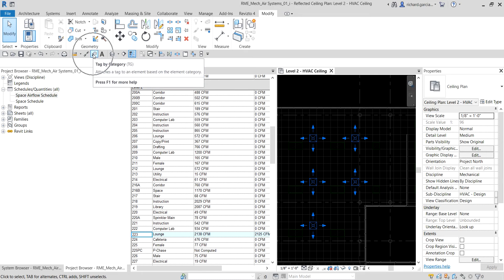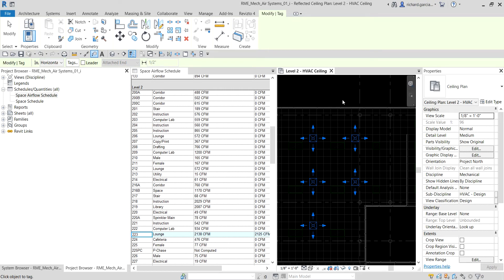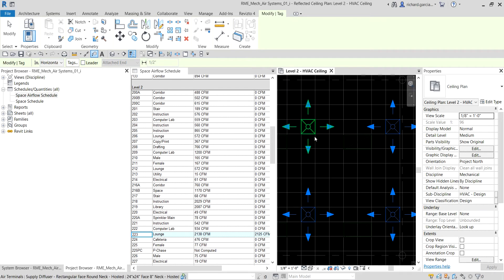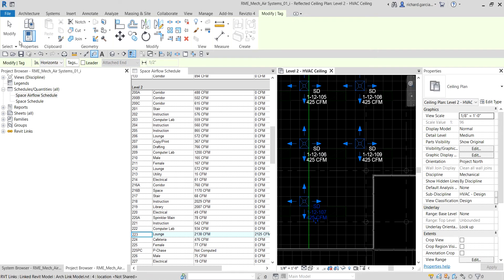Next, I'll tag the diffusers using Tag by Category — click that or type TG. If there's no loaded tag family in the project, a dialog box will appear asking you to load one. Select Yes, browse to your diffuser tag file, select it, and click Open. Make sure the Leader option is unchecked before clicking. Once loaded, you're ready to tag your air terminals in the project.